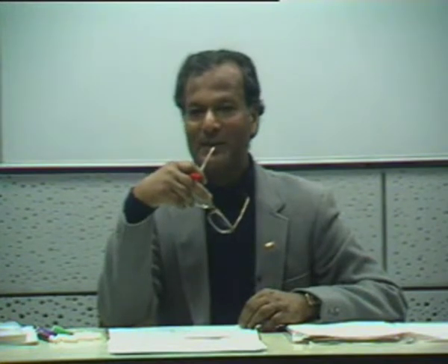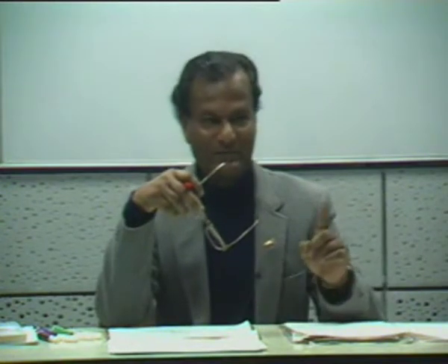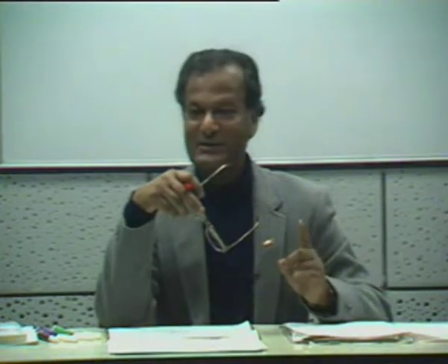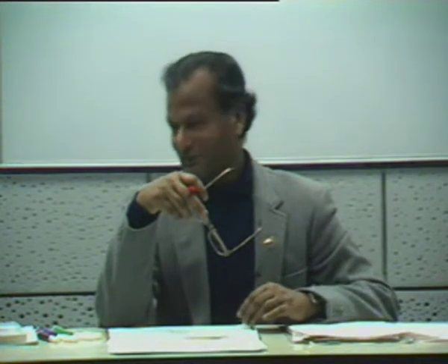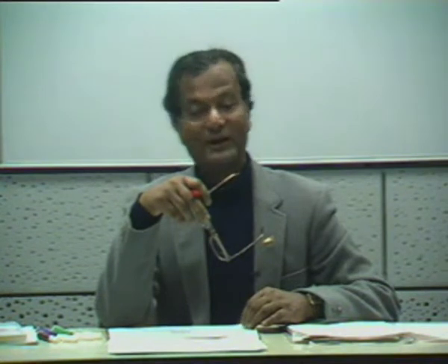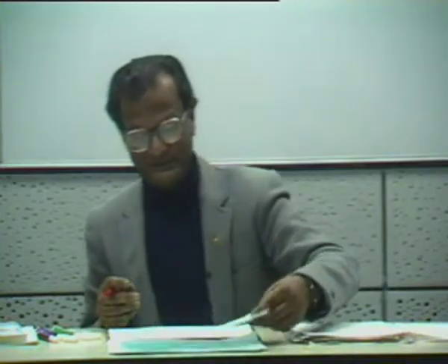Critically damped. Well, why not underdamped? Let's understand. If we have an underdamped system, then it keeps oscillating about the actual position, and we don't get the exact value in a small time. That's right. It takes quite a bit of time. The needle goes on oscillating, and then finally it settles to some value. Whereas if it is critically damped, then it reaches the final value. If it is overdamped, then it takes a very long time to reach a steady state. And therefore, these concepts are important.